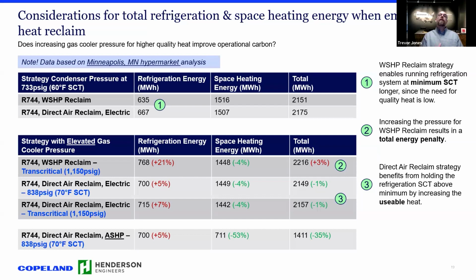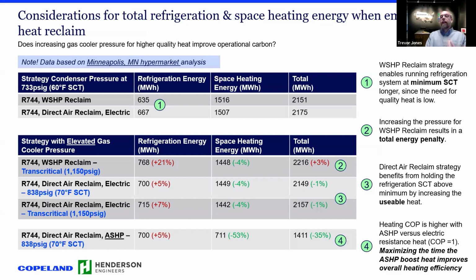Some of that was based on our system architecture. We were looking at a lot of outside air being brought in directly over a coil, and there you don't need to have it as hot to pull all of the energy out that you can. So when we then added the air source heat pump versus the electric resistance, we saw a marked decrease in the total energy use. And that is directly related to the higher COP of the air source heat pump versus electric resistance heat.